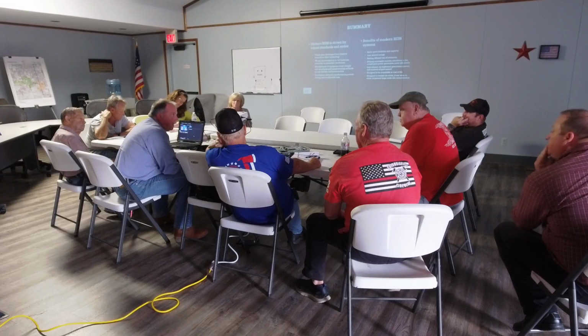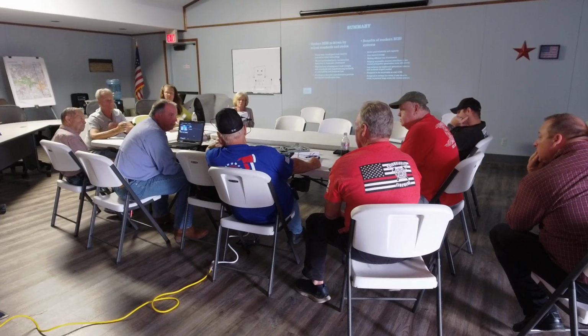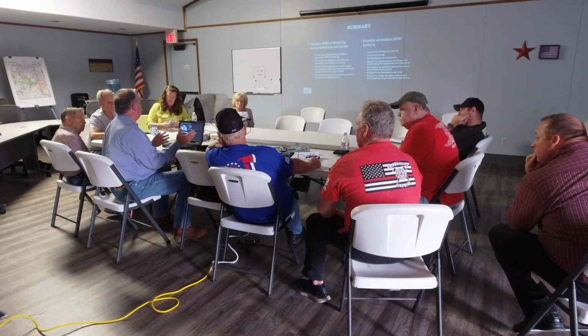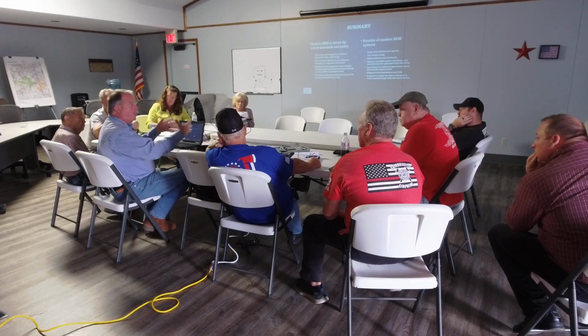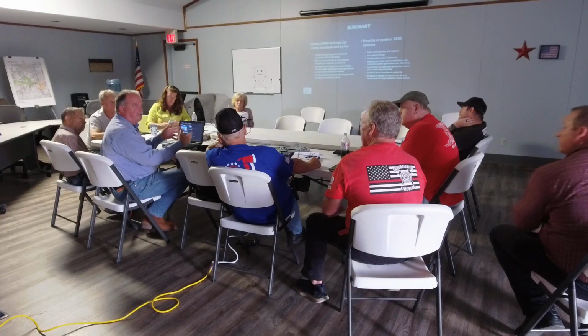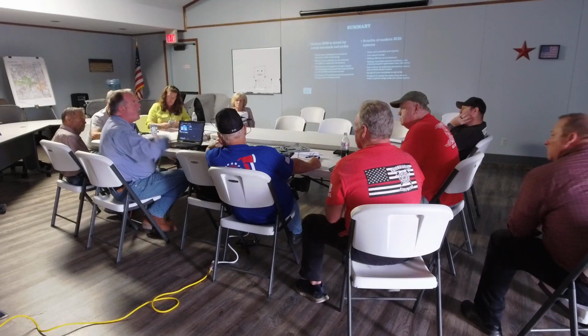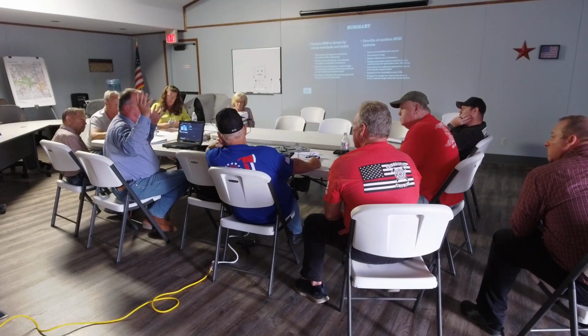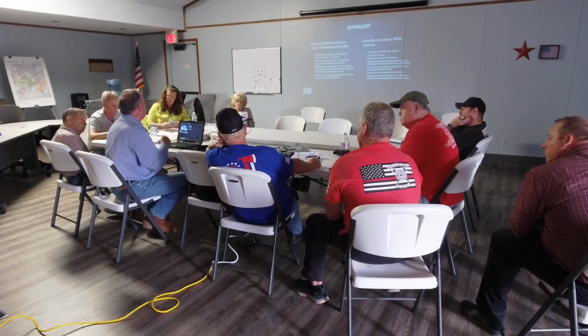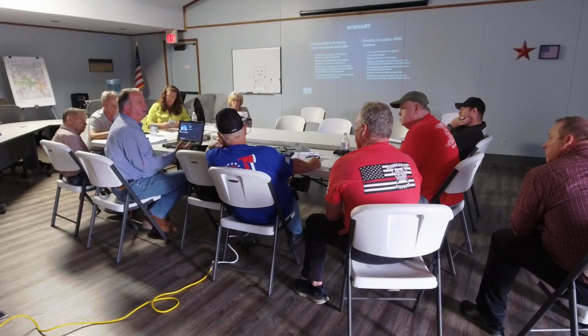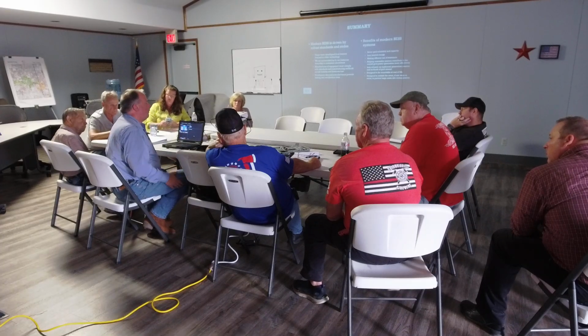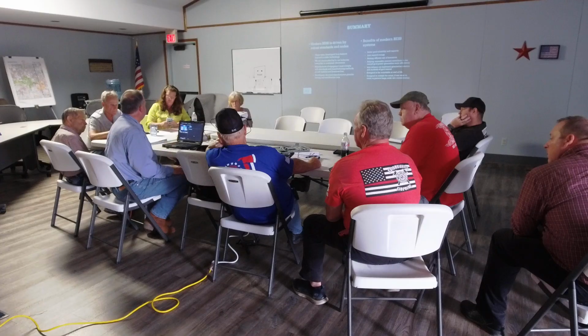They installed those batteries in an old turbine hall in California. A turbine hall is where they used to have big turbines run by steam, turning a generator. It's a massive concrete building, so think about what happens to concrete in the sun for hours and hours. My first thought goes to how they were dealing with the thermal issues, because there's a lot of heat in that concrete. Being nickel manganese cobalt, it's not as tolerant to those temperatures as lithium iron phosphate is.